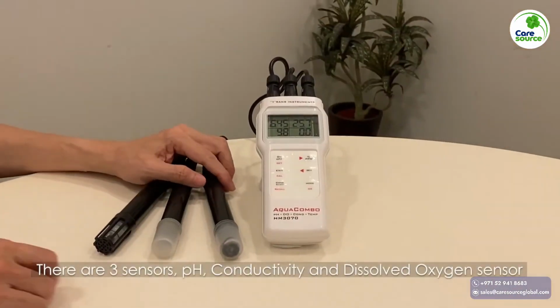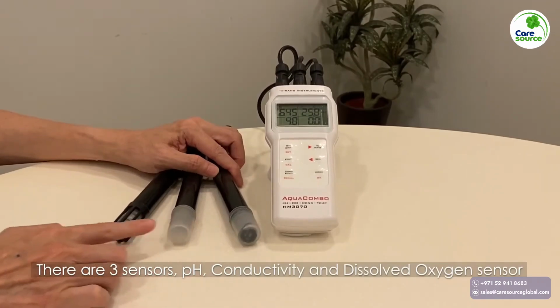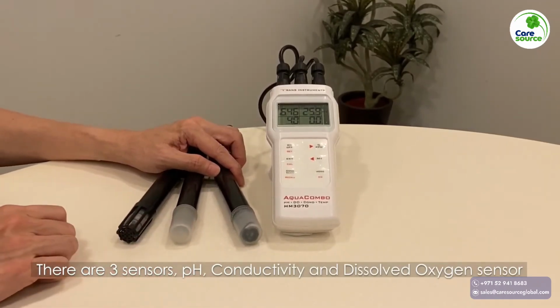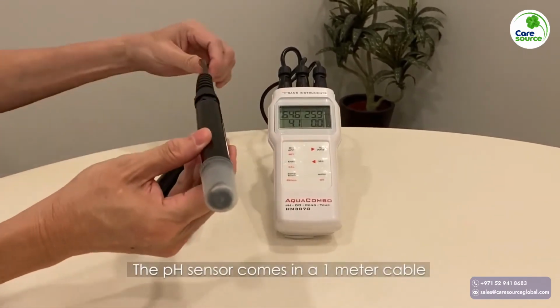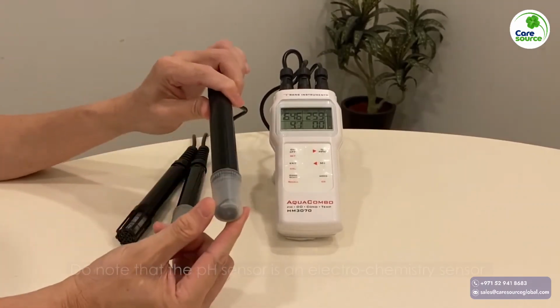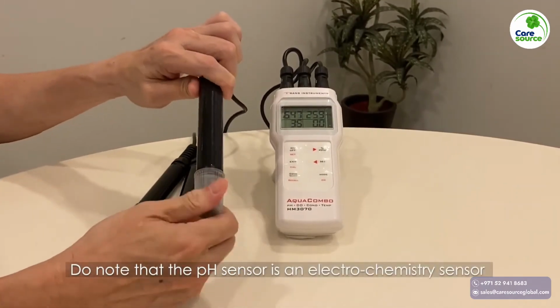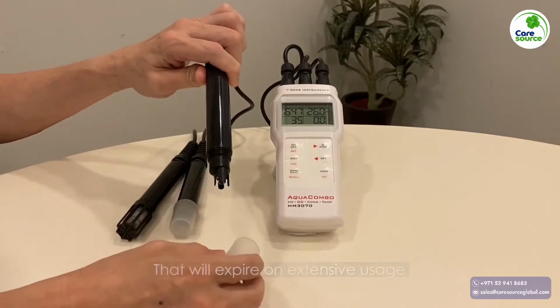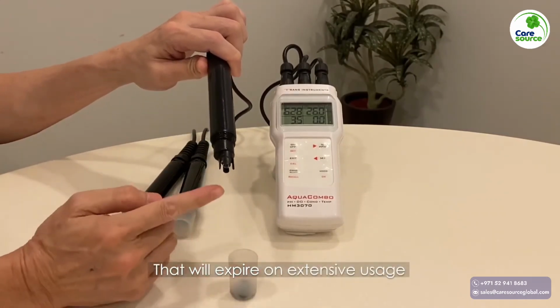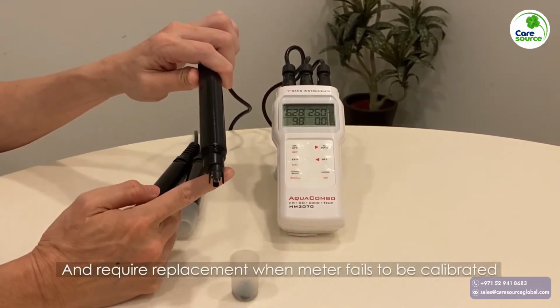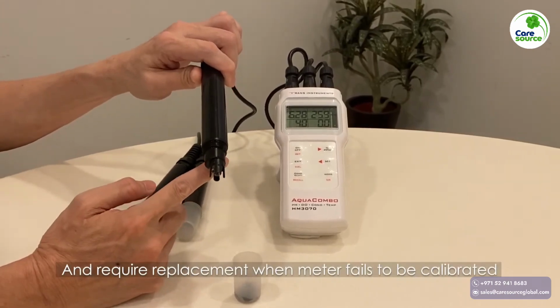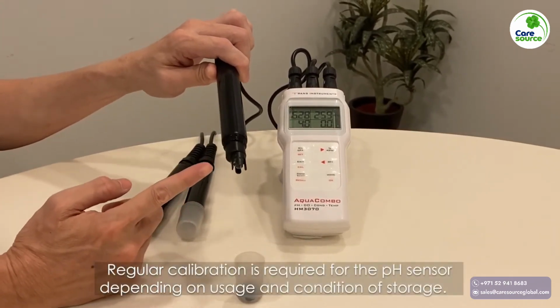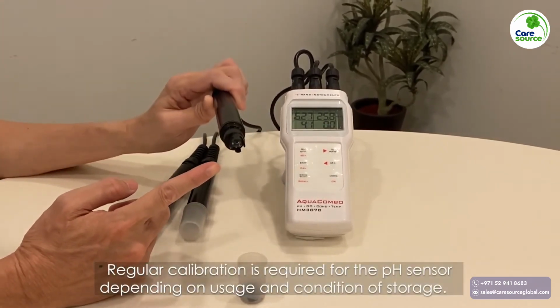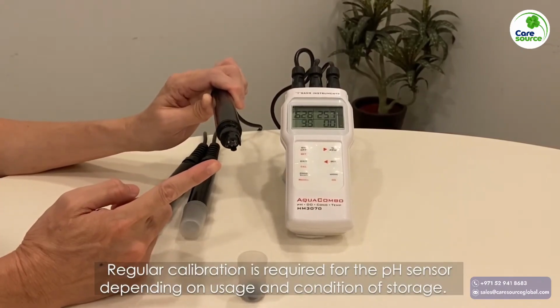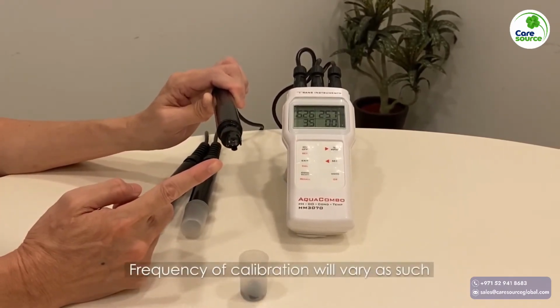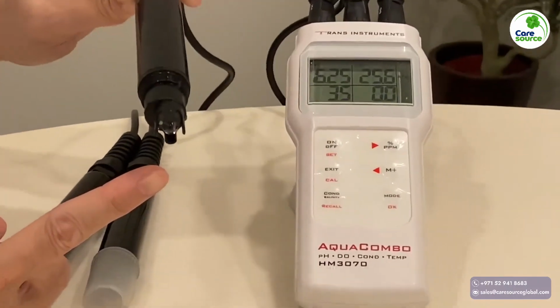There are 3 sensors: pH, conductivity, and dissolved oxygen sensor. The pH sensor comes in a 1 meter cable. Do note that the pH sensor is an electrochemistry sensor that will expire on extensive usage and require replacement when the meter fails to be calibrated. Regular calibration is required for the pH sensor depending on usage and condition of storage. Frequency of calibration will vary as such.